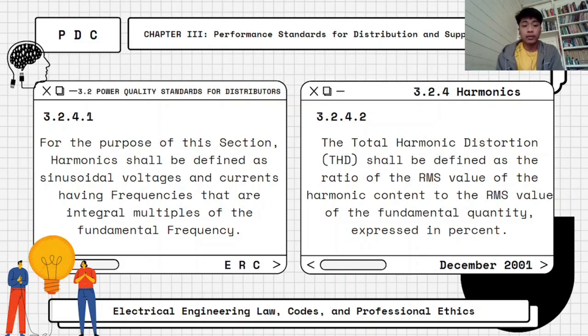Harmonics is defined as sinusoidal voltages and currents having frequencies that are integral multiples of the fundamental frequency. The total harmonic distortion, or THD, is defined as the ratio of the RMS value of the harmonic content to the RMS value of the fundamental quantity, expressed in percent.